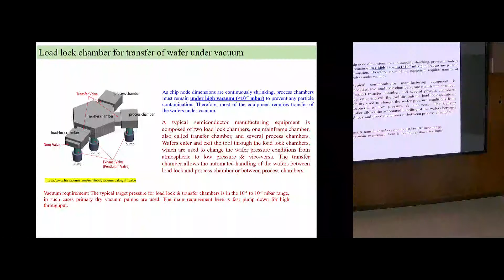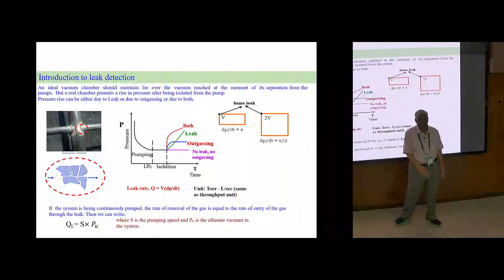So this is how the leak rates are there. Whenever there is a leak in a small volume bulb, no problem, or you can throw it. But if it is ultra high vacuum, the same leak, a small size hole, matters. If the chamber is bigger, the pressure rise rate will be small. Okay, with a big 1 lakh rupee salary, if 1 paise goes daily, you don't bother about it. But if your salary is 10 rupees and 10 paise is going, you have to bother. So where it is tolerable or not tolerable, you have to decide. Once you decide, you measure the pressure, another 2 minutes.